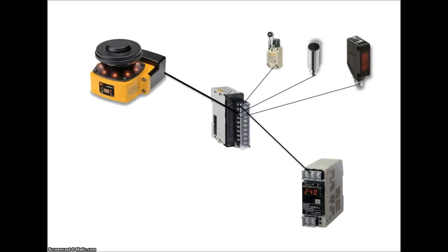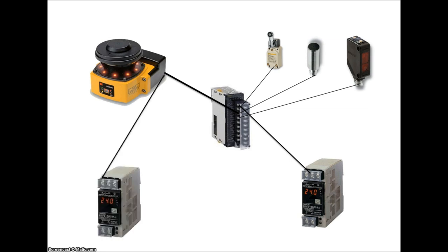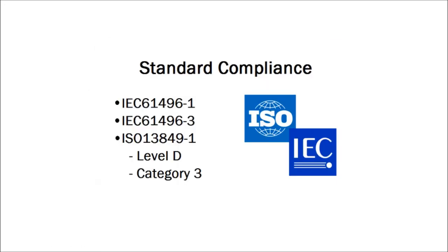Laser scanners, as with light curtains, by standard, need to be ran off their own dedicated power supply. This unit is considered a type 3 safety laser scanner and complies with IEC 61496-1 and IEC 61496-3. Under ISO 13849-1, it is performance level D and category 3.